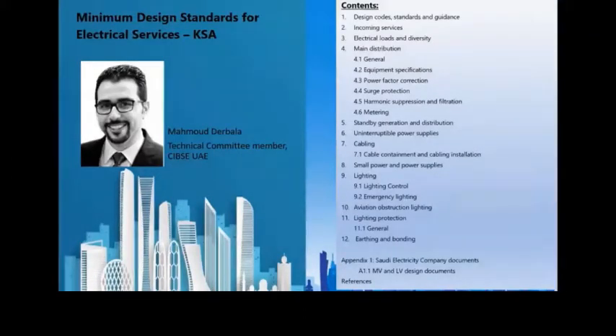Emergency escape lighting design guidance is provided along with Saudi civil defense requirements for backup duration, which is 90 minutes in KSA. There's also a brief about emergency luminaire types and system types, referencing Saudi Building Code requirements for recording, testing, and circuiting.